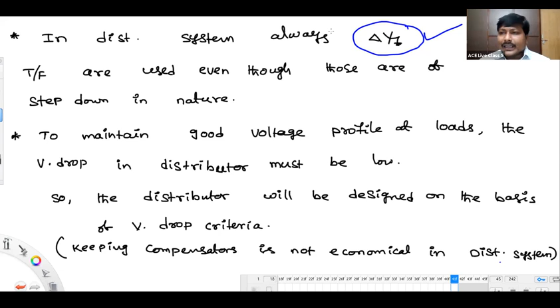Yes, load. See, actually, current rating is also going to be considered definitely. We have two things. One is the voltage drop criteria. Next one is the current rating. The primary criteria is voltage drop. The secondary criteria is current rating. So definitely current rating has to be satisfied.